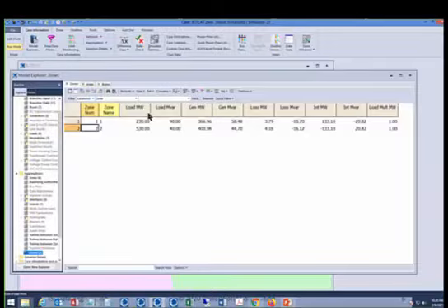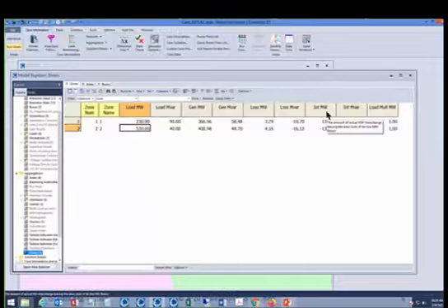So we can see it does the accounting of the load and generation that's in the zone, but there's no AGC function for the zone. So it's not going to try to hold exports at a specified value. It's just going to show you what the exports are. In this case, it's the interchange megawatt. So that's how much is flowing across the tie line from 1 to 2. Because we only have 2, the numbers are the same, but with the opposite sign. It shows that for megavars as well.